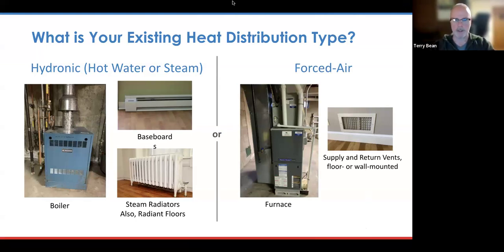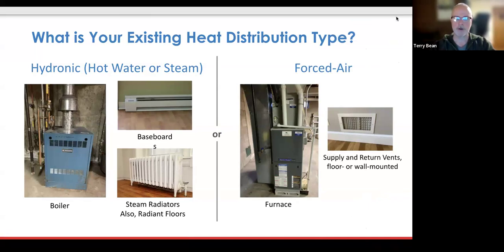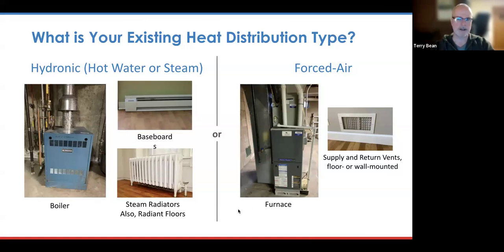So there is one type of hydronic system that is referred to as hydro air. And what that means is one of the zones off of the hot water boiler will actually heat up a heat exchanger inside of ductwork, and then that exchanges into hot air. So that could be a case where you actually have a boiler that is distributed through ductwork. Why someone would want to do that is if they added, say, heating to a second floor and AC at the same time, it allows them to do both through the same ductwork. So that's one caveat in terms of hydronic delivery.